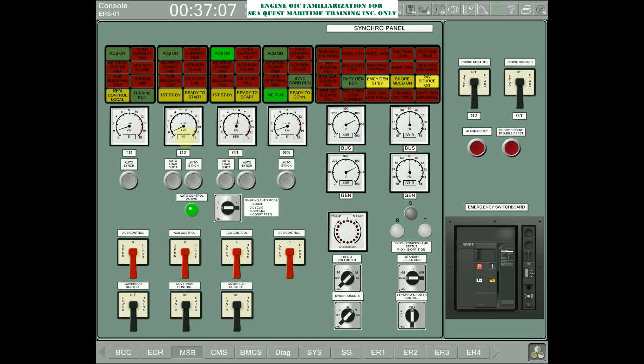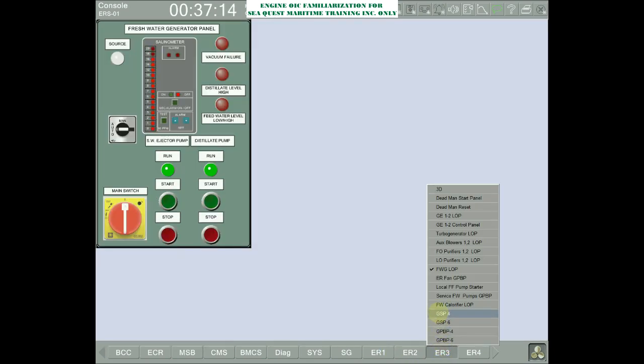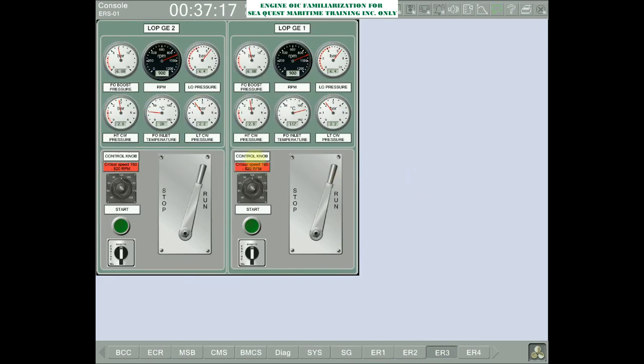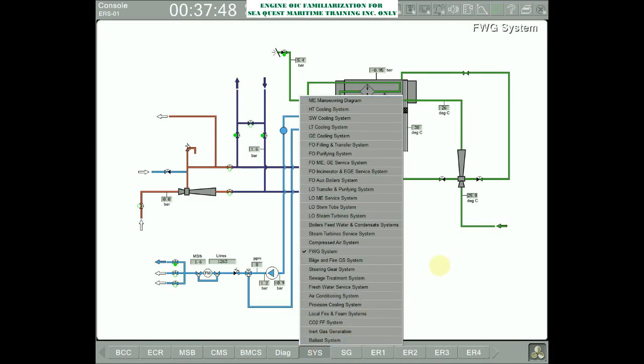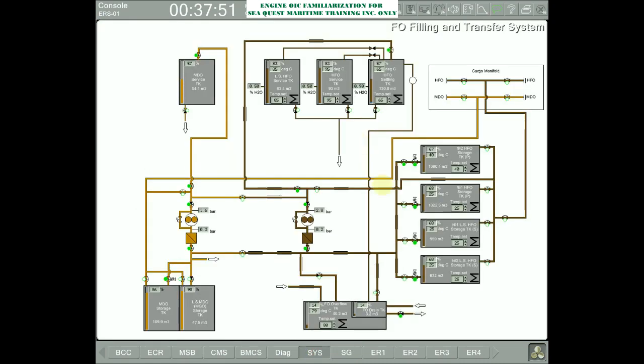Okay, so once the number 2 GE has no more load, let's go to ER3, select GE1 and 2 and stop number 2 DG, by pressing the handle, moving the handle to stop condition. Okay, once the RPM is 0 on number 2 DG, put back the handle to run. Now go to SYS. Let's see if the cooling is running. Okay, so it's running.